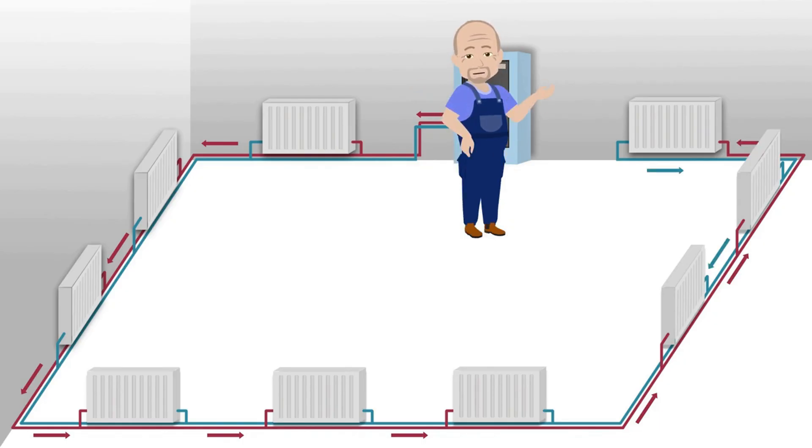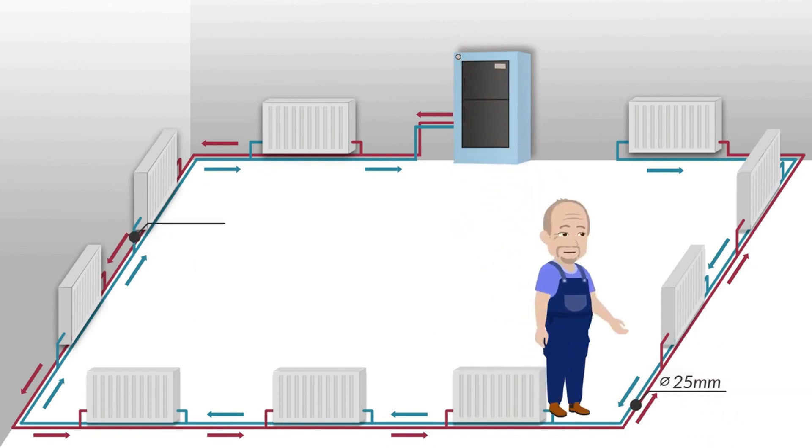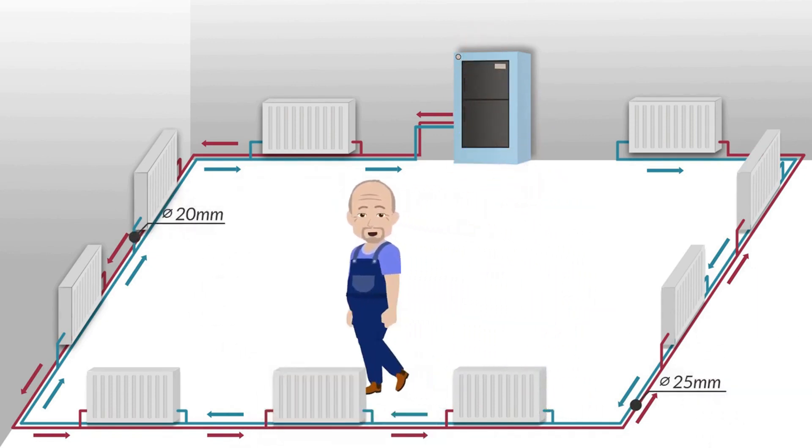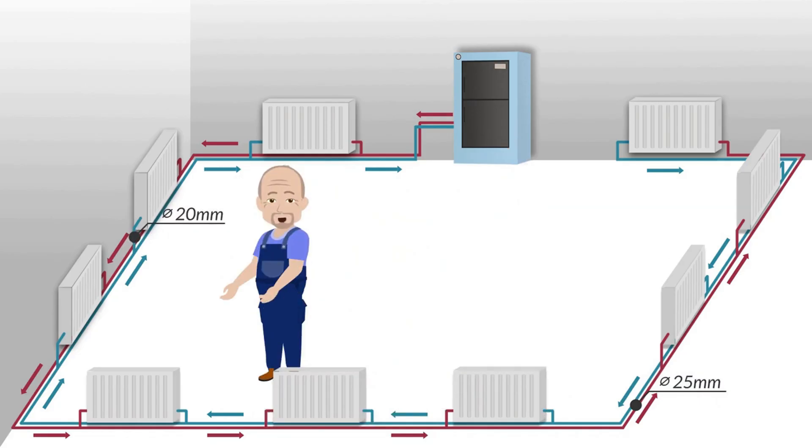And through the second pipe, the cooled coolant, collecting the return from all the radiators, heads back to the boiler. Most often in this installation system, the supply and return pipes are 25 millimeters in diameter and the heaters are directly connected by a 20 millimeter diameter pipe.